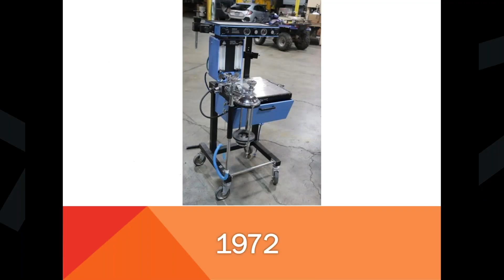Speaking of being slumped down, the cap here was unscrewed, so the vaporizer was pumping all this anesthetic gas out into the room in massive volumes. Luckily I was able to get over there and screw it down. Then I went to the flow regulators on the wall that had oxygen that weren't being used, and I opened them wide open, and I just hung out to make sure everyone was going to be okay, because I didn't want to turn the machine in the room back over if they were going to have a problem. Fortunately, everyone came out of their little nap, and then the case went on. I guess just dumb luck. But that was a pretty intense anesthesia moment to walk into, because the room was already full of sevoflurane and getting worse.